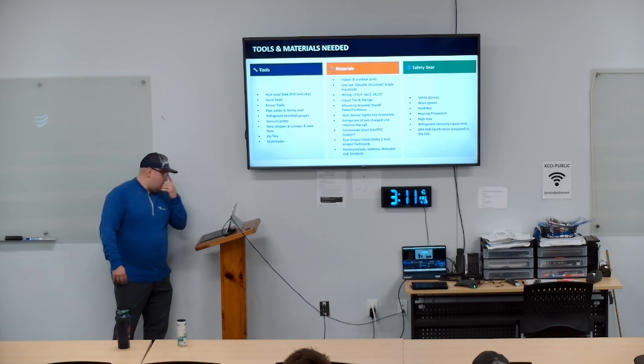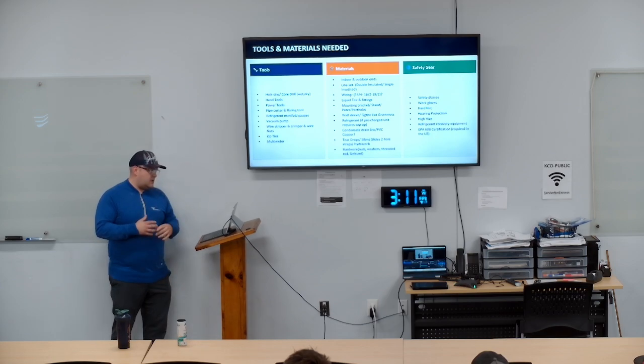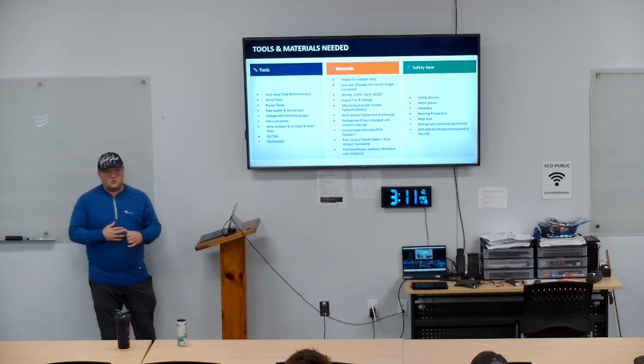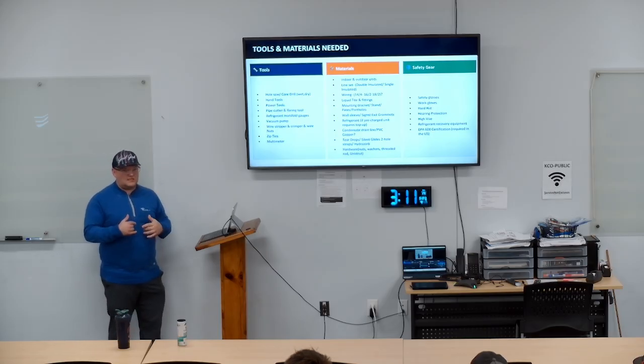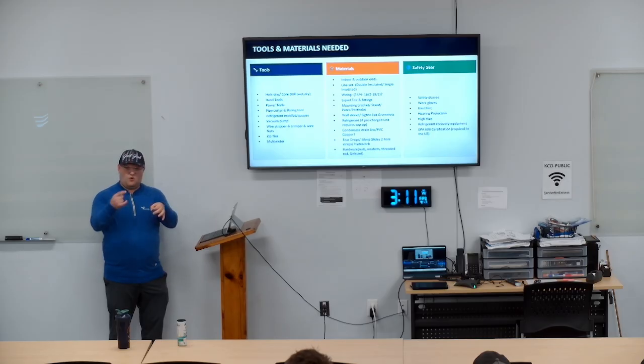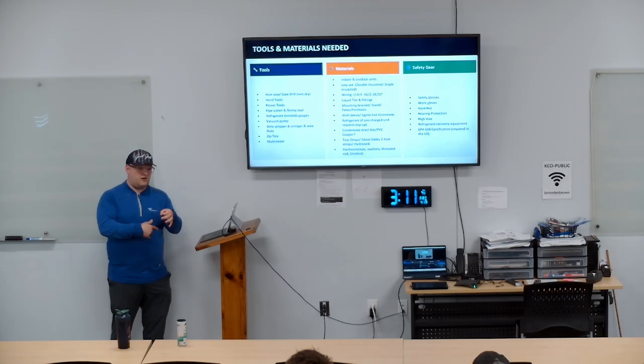Mounting brackets. Well, I'm sorry, let's go to liquid tight. That's simple. Anything outside, it's weatherproof. So any wiring we do outside, for you piping guys' sake, know that we have to use seal tight. If it's outside, it goes all the way back into the building. We don't leave bare wire outside. If we do, that's going to break. If you leave bare wire out and the seal tight's open, water's going to get in, and then water's going to freeze in the winter, and you're going to mess up the communication with the unit.